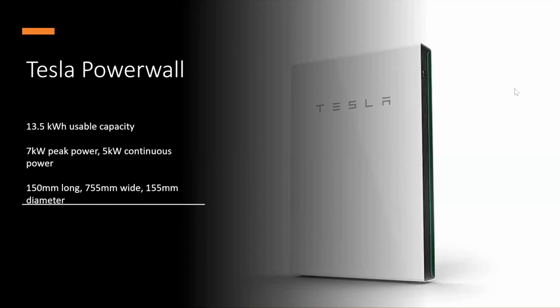But if you're looking to do a whole home application, that's fine, we can do that. We just need to daisy chain these batteries together. That's what's really cool about the Tesla Powerwall, you can link multiple batteries together. So instead of having 13.5 kilowatt hours of capacity, you can double that to 27 kilowatt hours, and so forth. One of these batteries, the height is 45 inches, they're 30 inches wide, and the depth is about 6 inches. They can be mounted on the wall or on the floor.